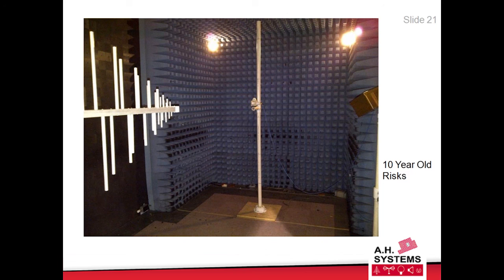How old would you say this test setup was? Even since they put on the high frequency capability with these absorbers, you can see there's a fair amount of wear and tear, where people putting tables in have been rubbing up against the absorber and worn out the tips. But this is not atypical, particularly of in-house testing, what's out there. The antenna, from this angle, looks pretty good, but it too was pretty much frayed around the ears and was quite old. But this is not atypical, and if you were in charge of this test lab, you should feel free not to treat it as a holy relic.